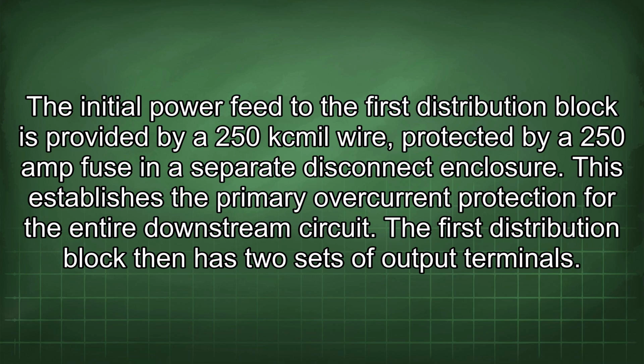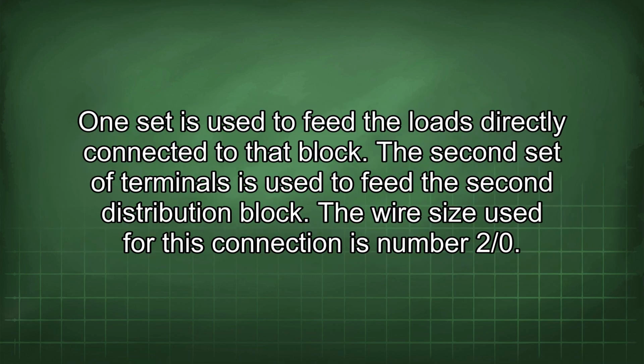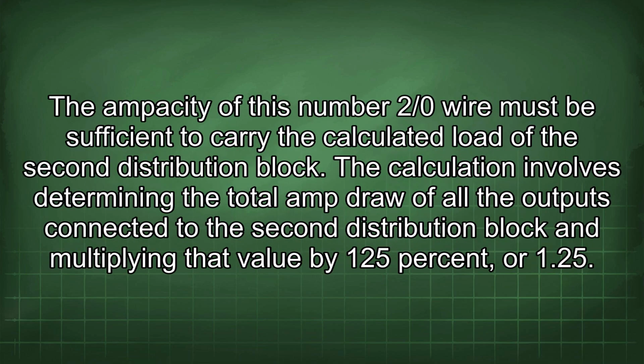The first distribution block then has two sets of output terminals. One set is used to feed the loads directly connected to that block. The second set of terminals is used to feed the second distribution block. The wire size used for this connection is number 2/0. The ampacity of this number 2/0 wire must be sufficient to carry the calculated load of the second distribution block. The calculation involves determining the total amp draw of all the outputs connected to the second distribution block and multiplying that value by 125% or 1.25.